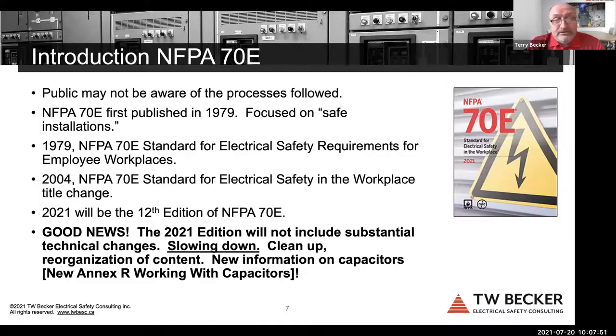Right. So the good news is that the technical content in the 2021 edition of 70E slowed down. It's more organizational and structural content and movement between articles 105, 110, 120, and 130. And likewise with Z462, with clause 4 and clauses 4.1, 4.2, 4.3. So not a lot of technical change, but the content flow, and I don't call that technical, it's the structural change in how 70E and Z462 advise an end user that would have an electrical safety program, right? You know, that this is what you should have in place.